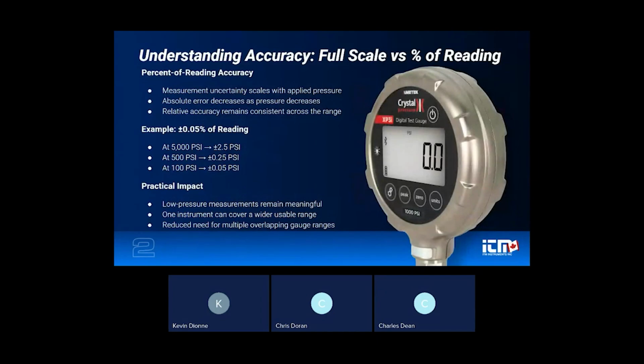offer to address the limitations of full-scale base accuracy, is to use % of reading rather than % of full scale. So with percent of reading accuracy, measurement uncertainty scales with applied pressure. So as pressure decreases, the absolute error decreases proportionately instead of remaining fixed across the entire range, right? So instruments like the one you see on your screen there, the XP3i, use % of reading accuracy combined with temperature compensation to maintain proportional accuracy under real-world operating conditions. So from a practical standpoint, this reduces the need for multiple gauges with overlapping ranges while still maintaining tight uncertainty at lower pressures. It also simplifies your technician's instrument selection, or if you're the technician, your instrument selection.